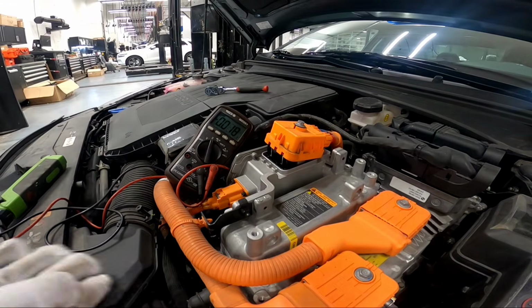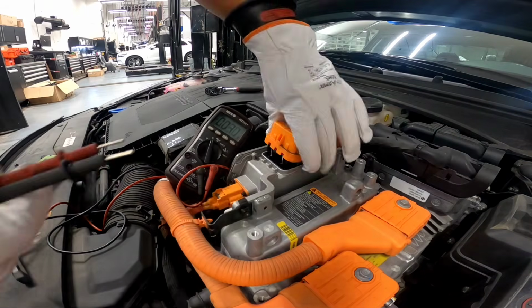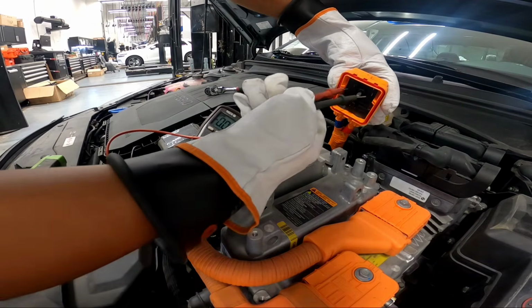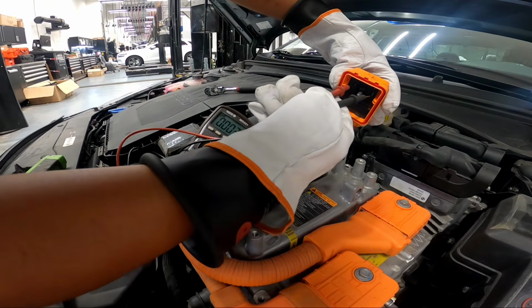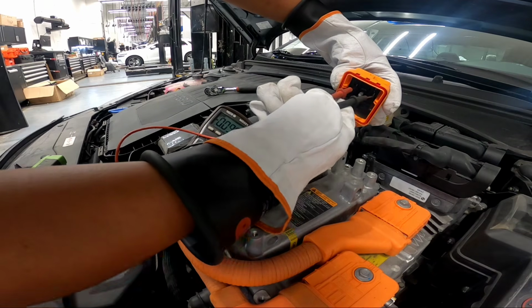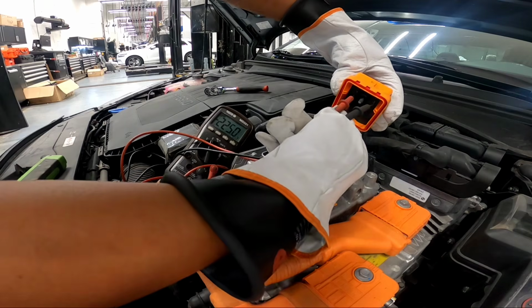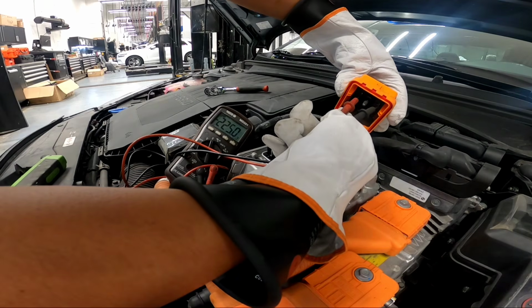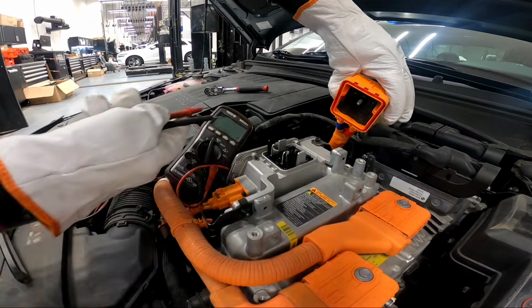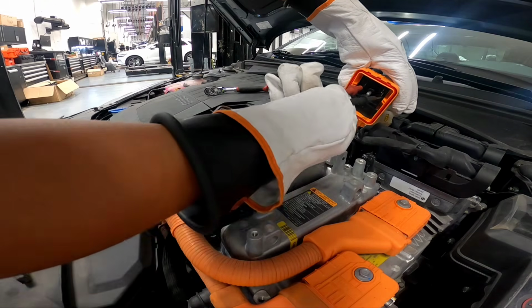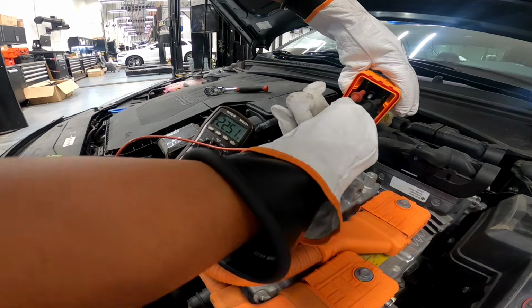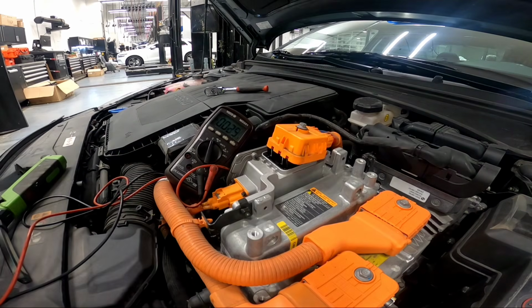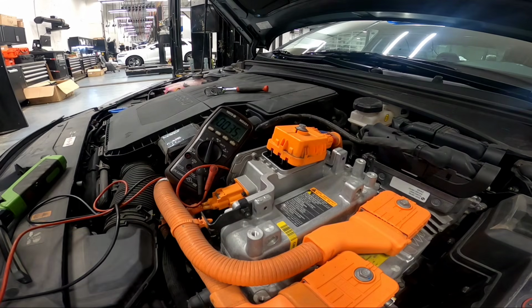Okay, I hope you guys can see the multimeter. Now I'm gonna probe both front first. Make sure they're reading 0 volts. I still got 225. You see that? 225 volts. That's not good. We already shut off the whole thing, and it should not be 225, because meaning something is on, something is sending that power going here. So that's not good.